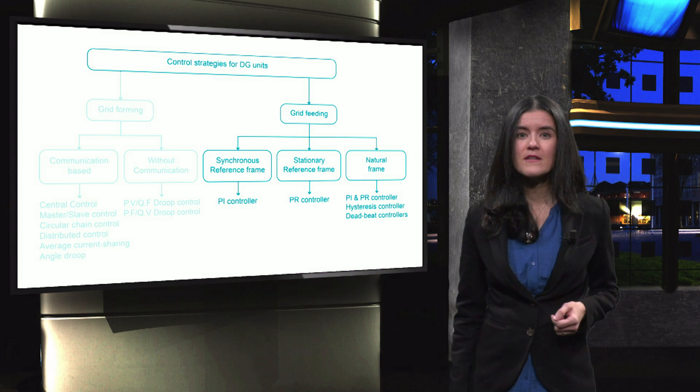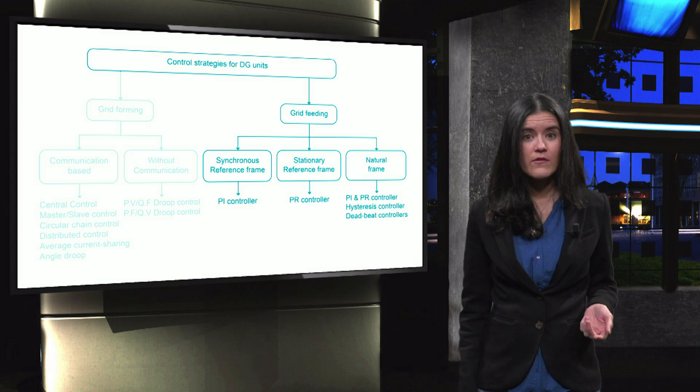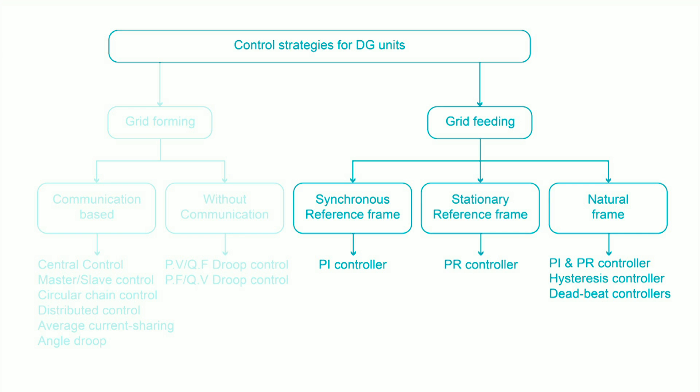Grid feeding types are typically implemented using a synchronous reference frame, a stationary reference frame and a natural frame. We have seen already that through a Clark-Park transform, it is possible to adapt a three-phase ABC signal into a stationary frame alpha-beta and then into a rotating DQ frame. The DQ rotating or synchronous reference frame is used when proportional integral controllers, also known as PI, are implemented. Stationary reference frame alpha-beta is used to implement proportional resonant or PR controllers. Finally, natural reference frame ABC can be used for a wide range of controllers, like hysteresis and deadbeat controller.